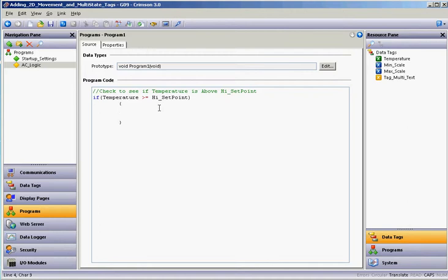So in this case, I'm going to do another text here, say turn on the AC. So then I'll go here, AC space one equal sign will assign the value, two equal signs will ask the question. So I'm just going to do one equal sign there. I'll put my cursor down here like this, enter, enter. So according to the logic here, if temperature goes above a high set point, it'll turn the air conditioner on. Okay, so the theory would be the air conditioner is running. Hopefully the room is getting cooler.